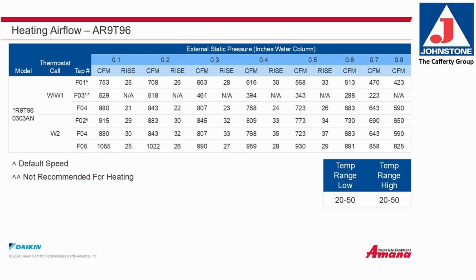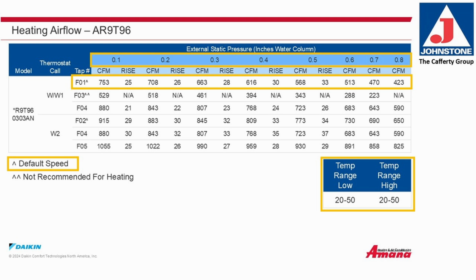Heating airflow. The top highlighted line shows external static pressure in inches of water column from point 1 to point 8. The next highlighted section that shows F01 shows the CFM and the temperature rise at different external static pressures for W1 default speed. The next highlighted section is F02, which is the default fan speed for W2. It shows the CFM and the temperature rise at the different static pressures. The recommended temperature rise range for both W1 and W2 are 20 to 50 degrees Fahrenheit.